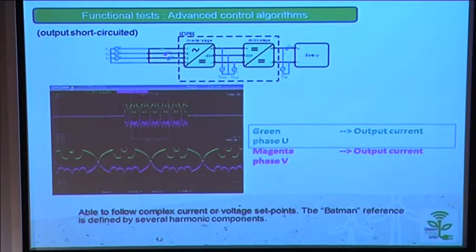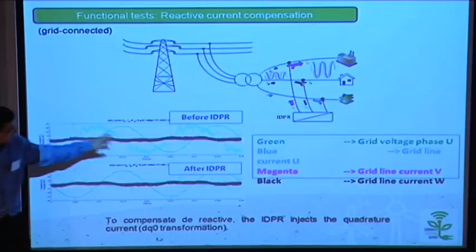We want the IDPR to have the capability to compensate reactive power. So this means that, for example, before we install an IDPR, this green line represents the voltage, this light blue line represents the current. Here we can see that both waveforms are shifted 90 degrees. After the incorporation of the IDPR, it is responsible for injecting this reactive power, and this means that the line is discharged from this responsibility. So we are using the current infrastructure for what it was designed at the beginning, which is to transmit active power, not reactive.